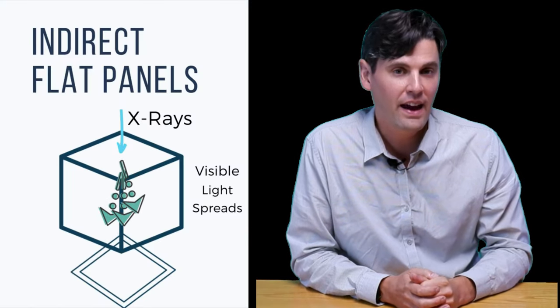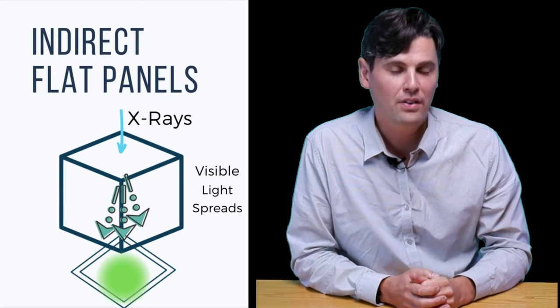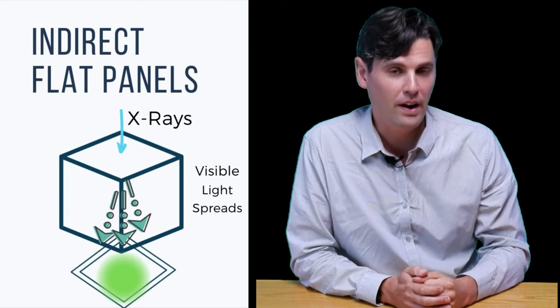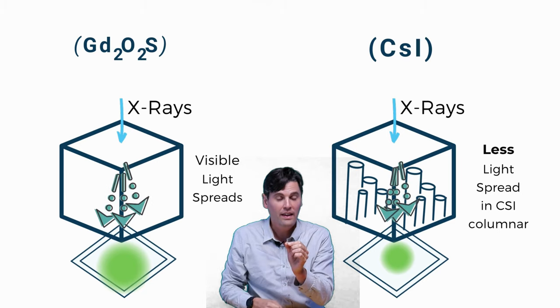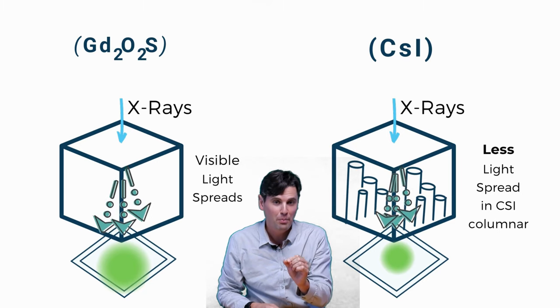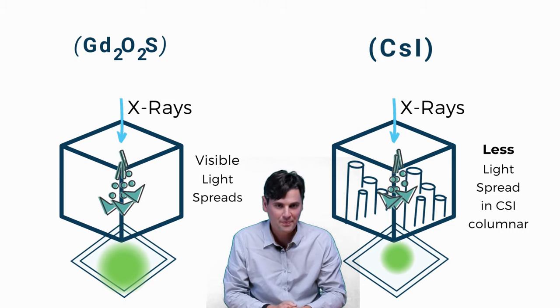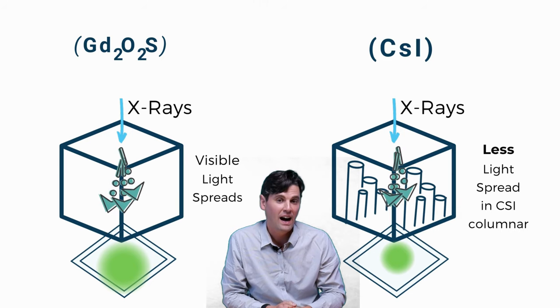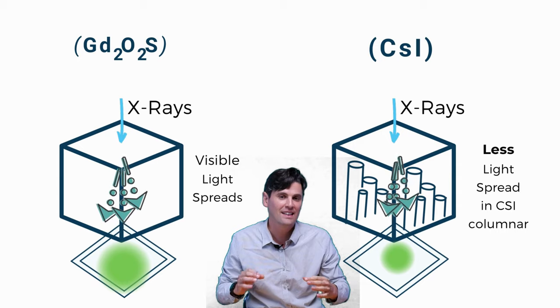That isotropic emission blurs the signal. An alternative that produces less blurring is cesium iodide — a crystalline structure where the crystals are grown in columns. Because the crystals are grown in columns, when the x-ray interacts, the visible light pings back and forth between the sides of the column rather than spreading. This gives higher spatial resolution because there's less light spreading.